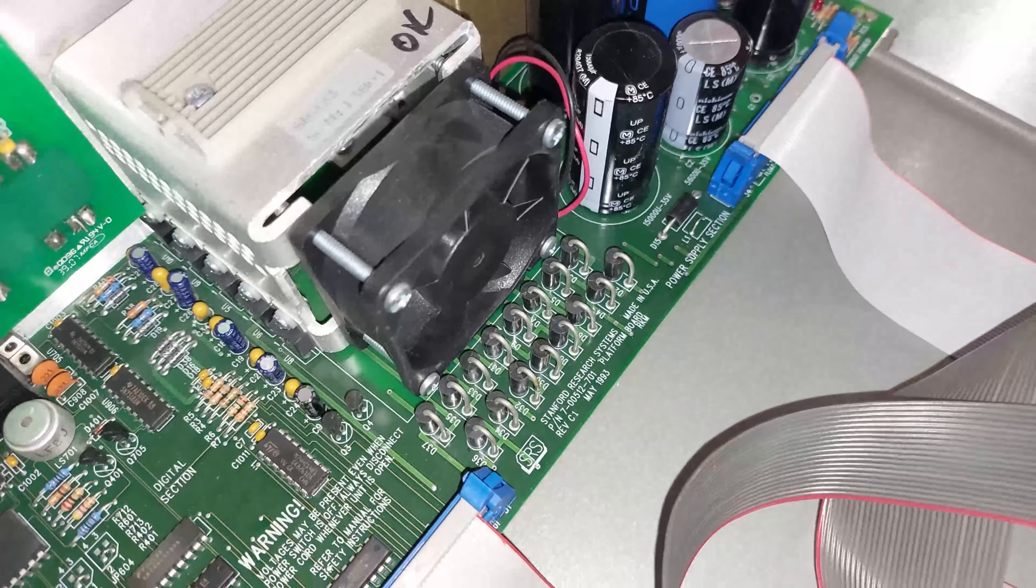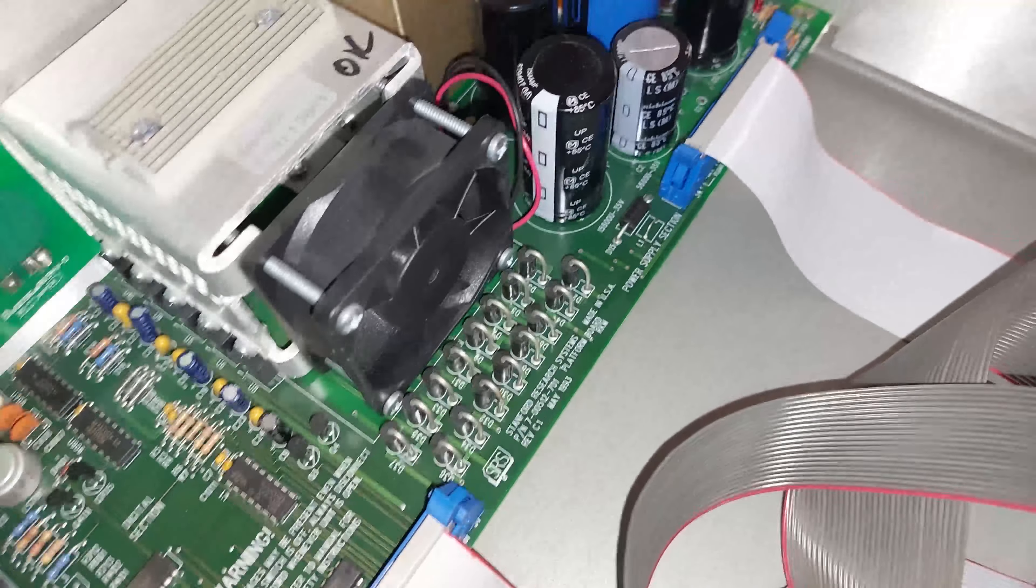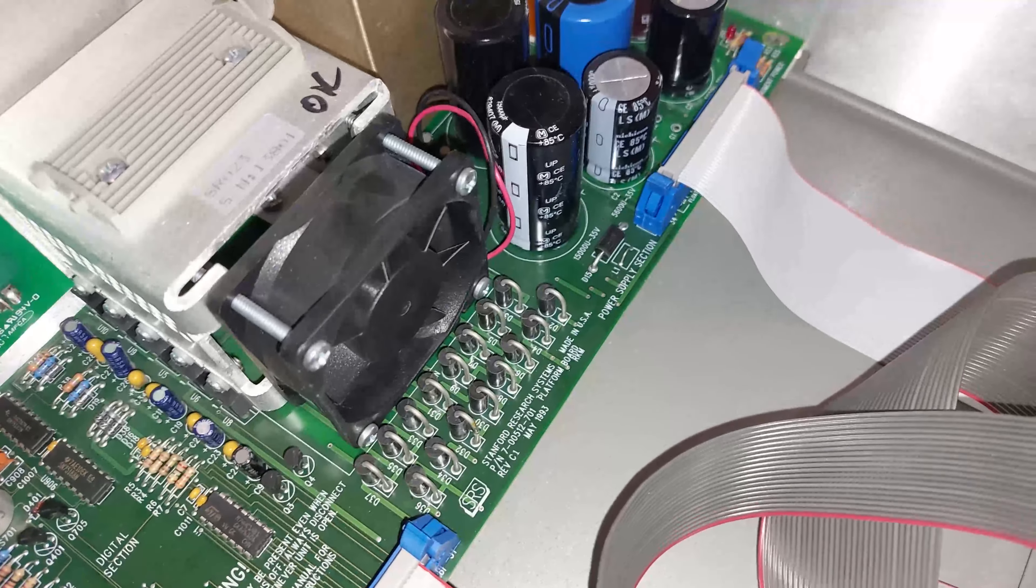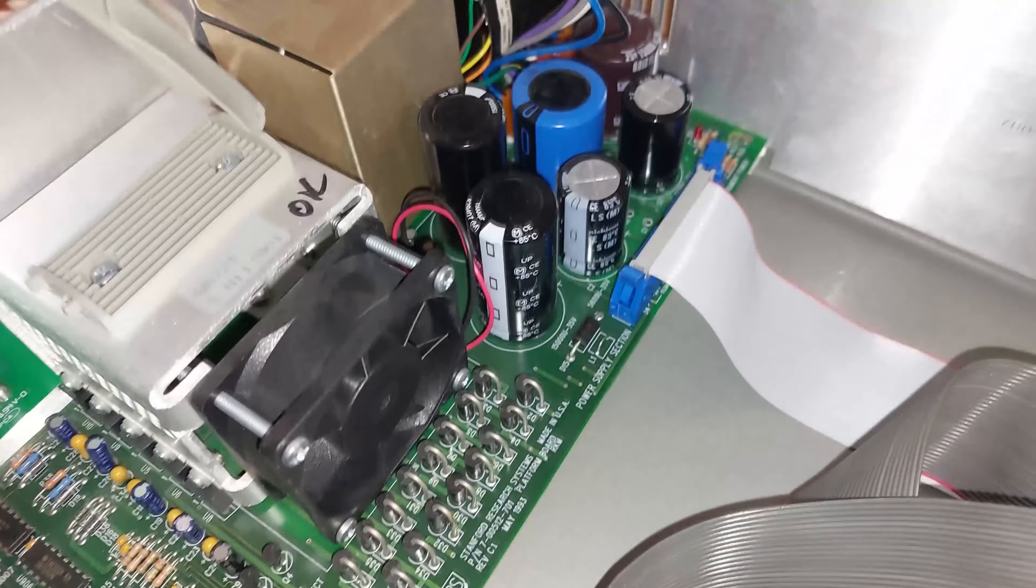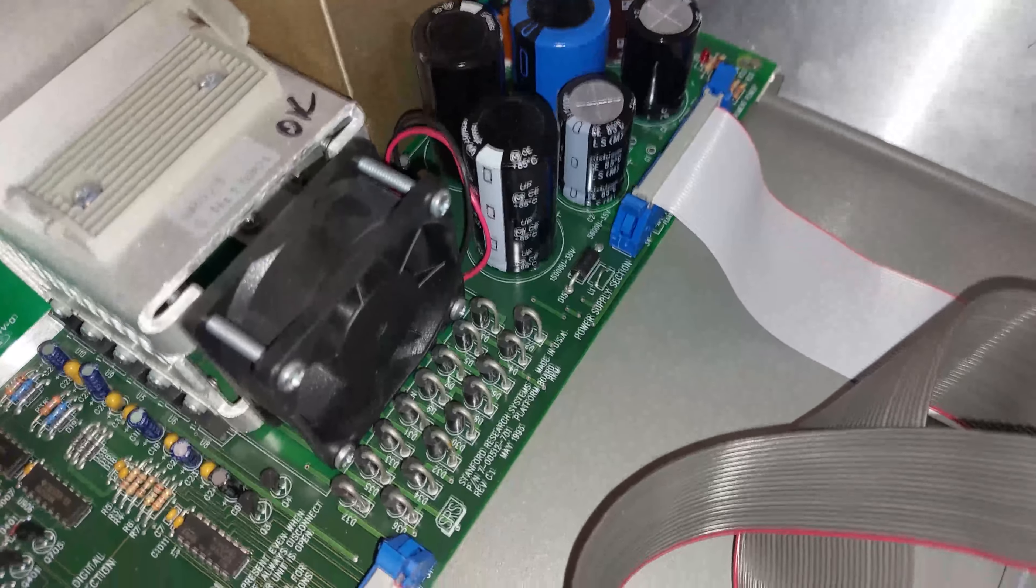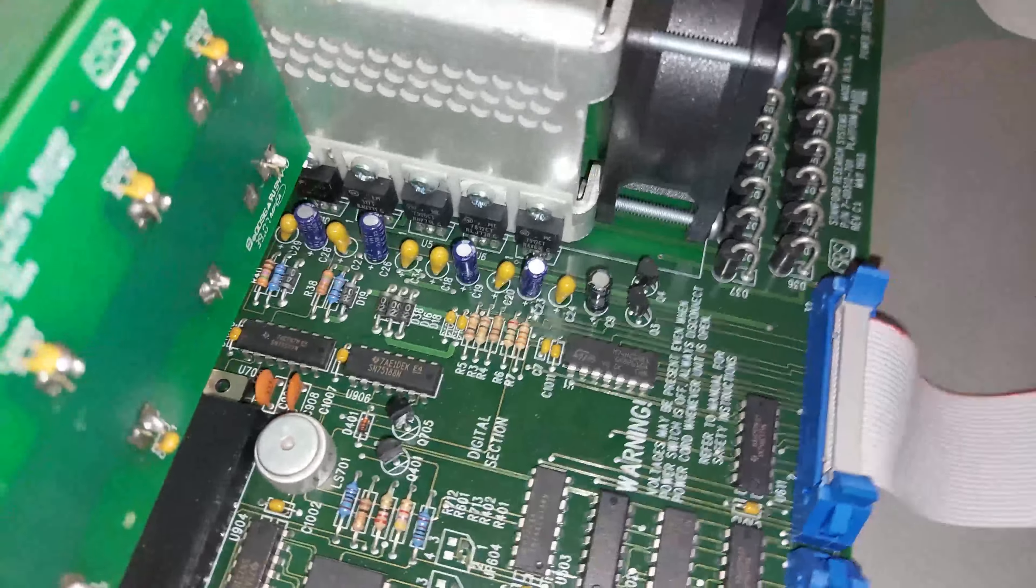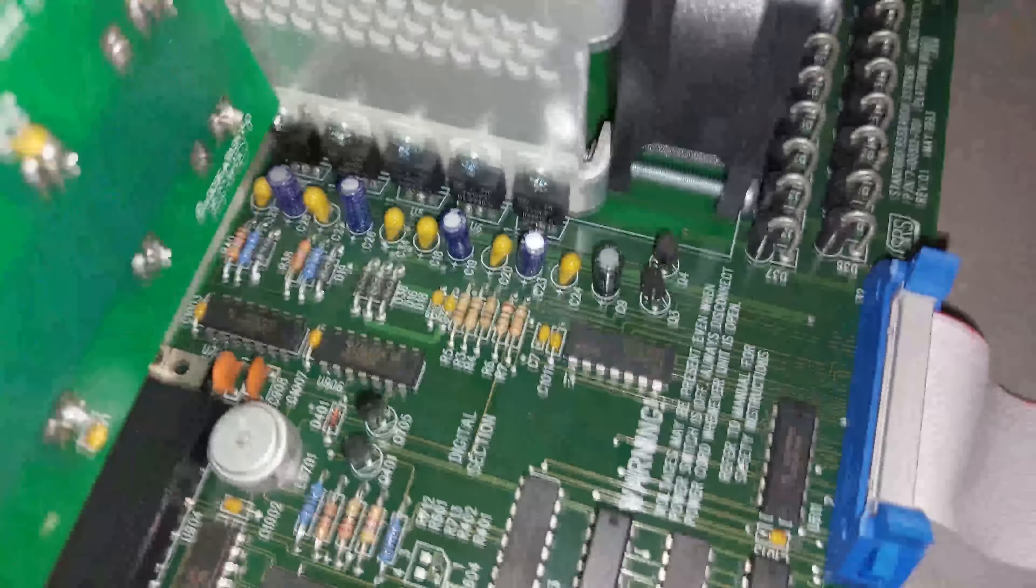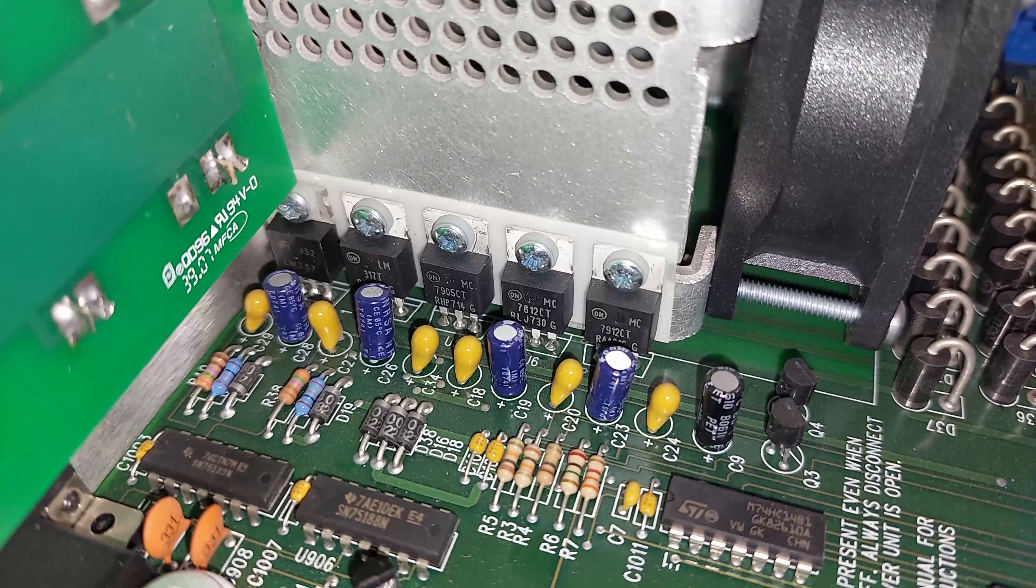That's a very weird way of doing it, but I assume that they had their reasons. The fan is cooling that shroud which is heatsinking the various voltage regulators.